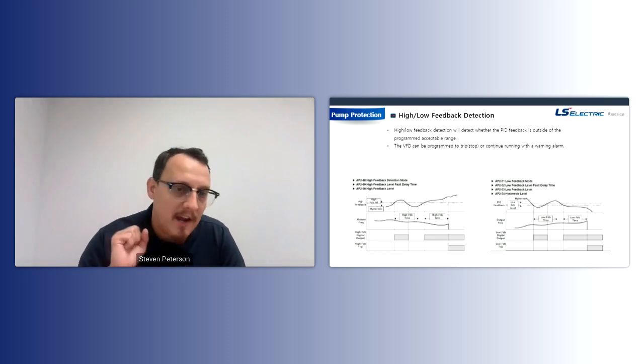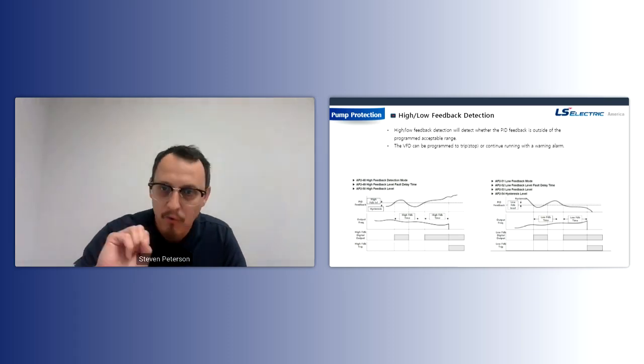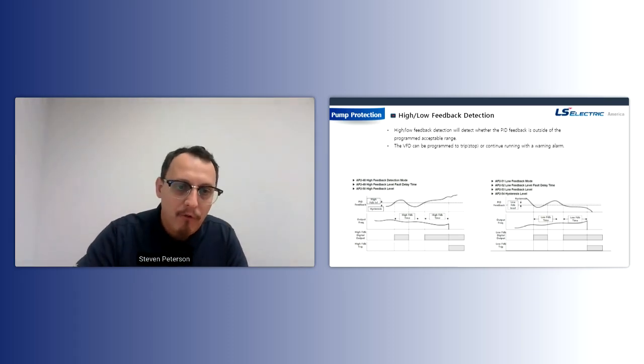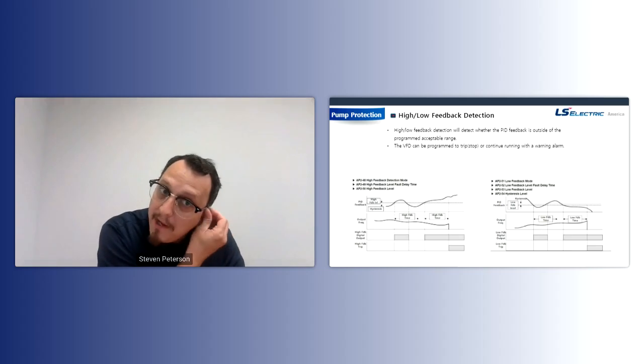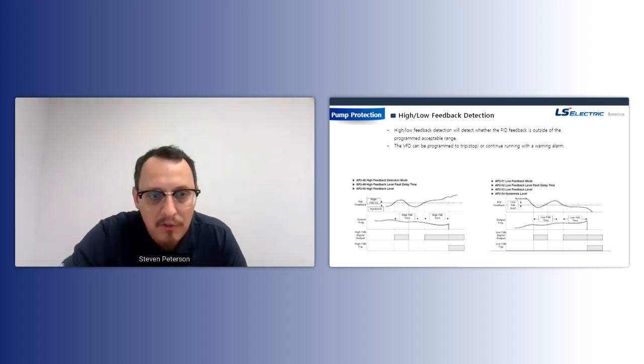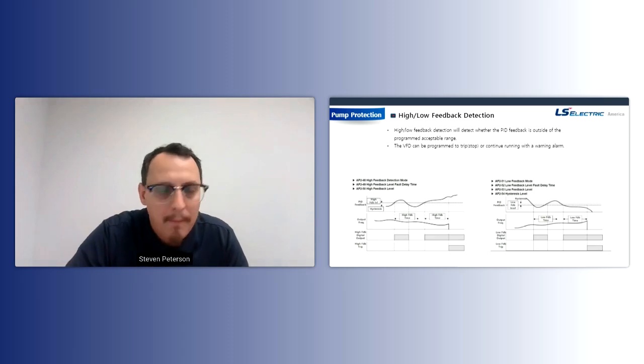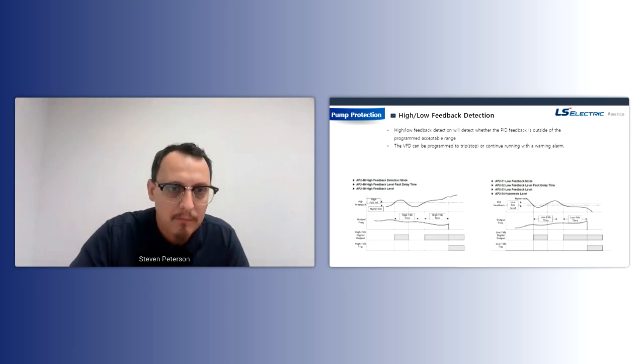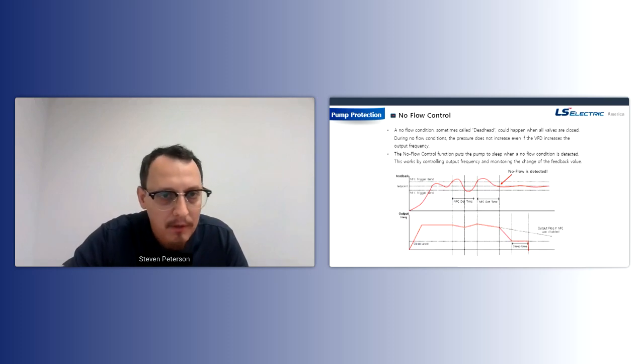So you could say, hey, if I hit 90 PSI, I want the drive to shut off. Or I want it to keep running. Or I want it to flash a warning alarm. You have a level and a delay for both high feedback and low feedback. You could set the drive to do a certain thing. Most likely you'd want it to stop before you overpressure your system. So this function can be enabled within the H100 Plus.